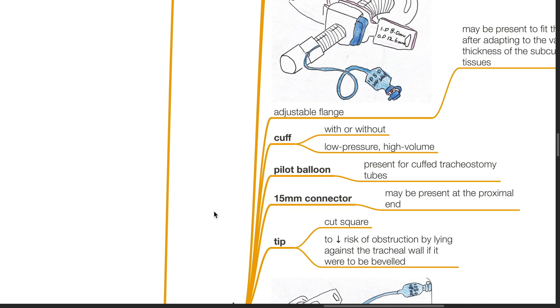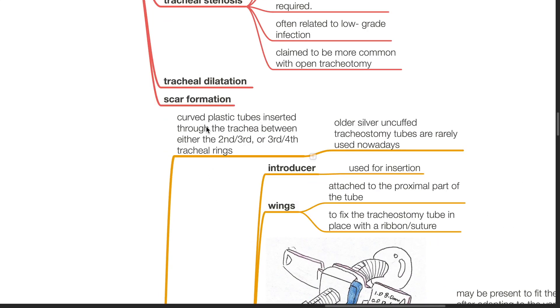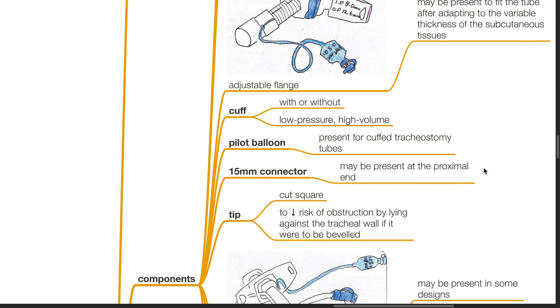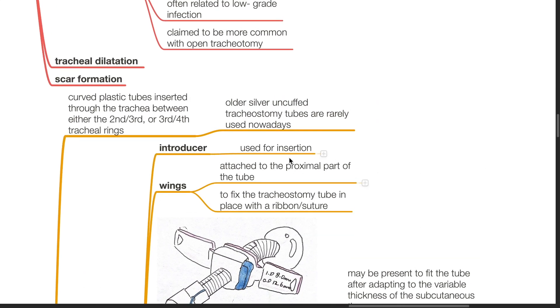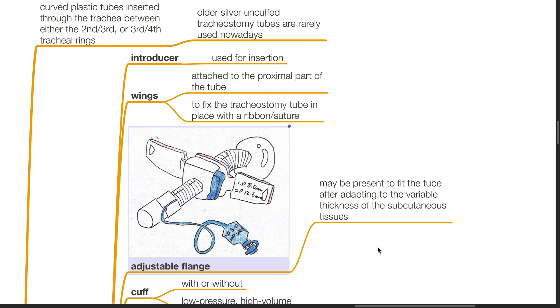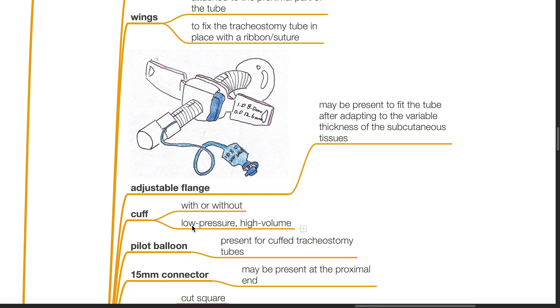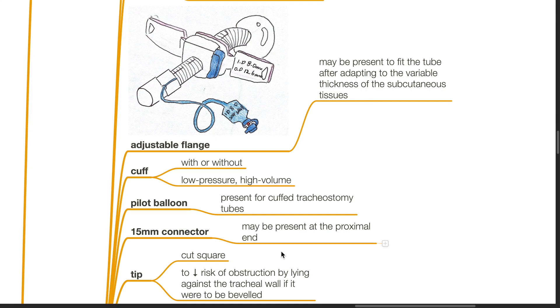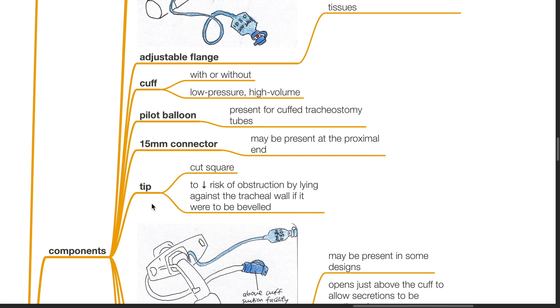Tracheostomy tubes are curved plastic tubes inserted through the trachea between either the 2nd and 3rd or 3rd and 4th tracheal rings. Older silver uncuffed tracheostomy tubes are rarely used nowadays. Components include an introducer used for insertion, wings attached to the proximal part to fix the tube with a ribbon or suture, and an adjustable flange to fit the tube after adapting to variable thickness of the subcutaneous tissues. A cuff may be present, which is low pressure and high volume, with a pilot balloon if the cuff is present. A 15mm connector may be present at the proximal end.